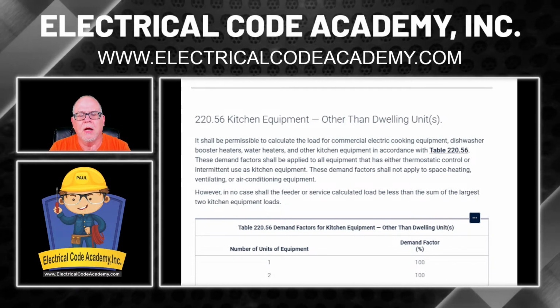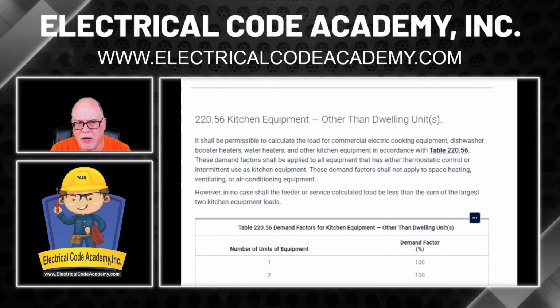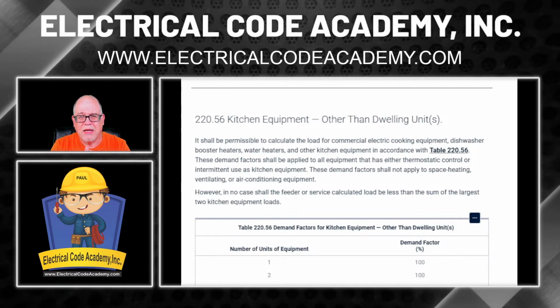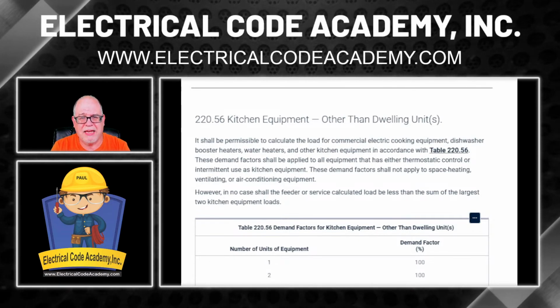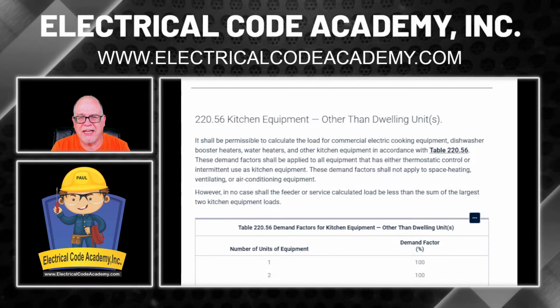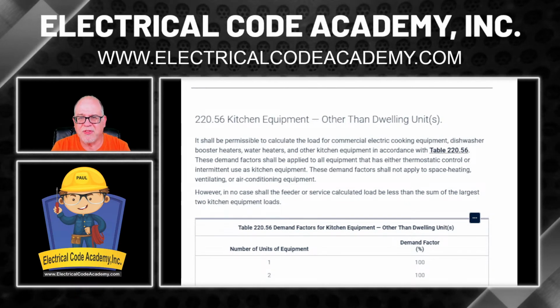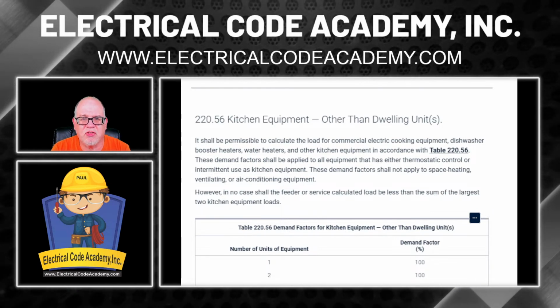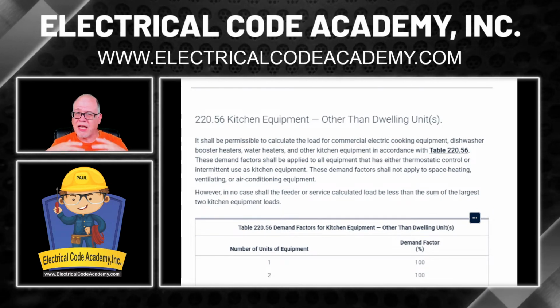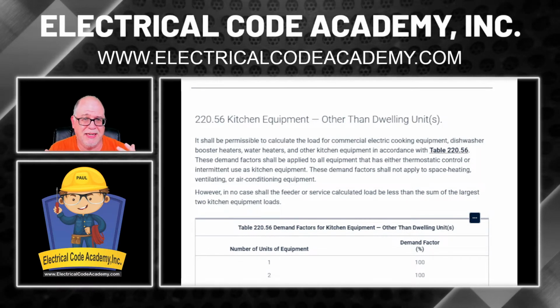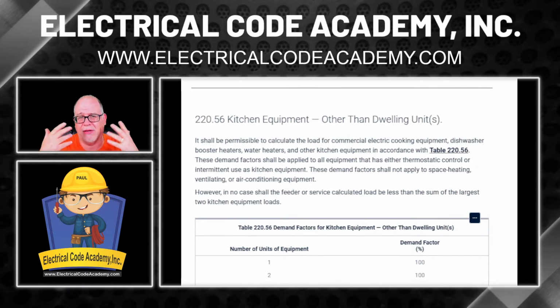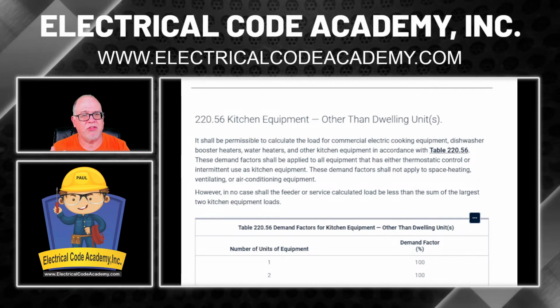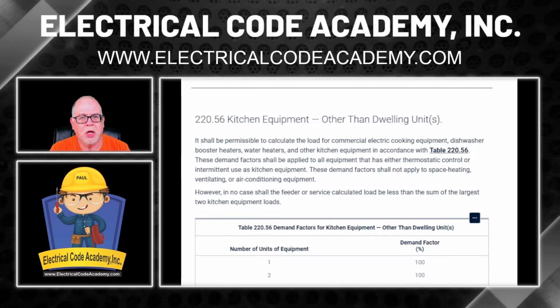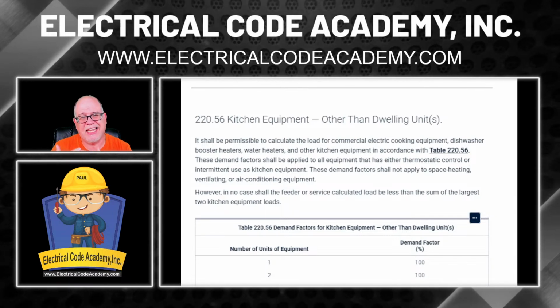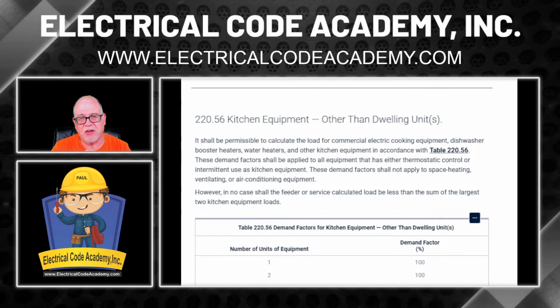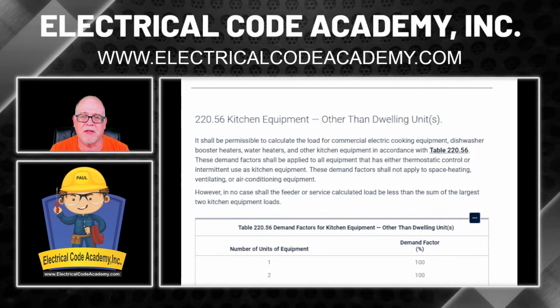Okay. One of the most important aspects I want you to be aware of is where it says, however. It says, however, in no case shall the feeder or service calculated load be less than the sum of the largest two kitchen equipment loads. Now, in the full calculation, it's probably never going to be, because we haven't even taken the other loads in the building into consideration. But in this question, based on your contribution, you also have to understand that the math we're getting ready to do can't be less than the two largest pieces of equipment.